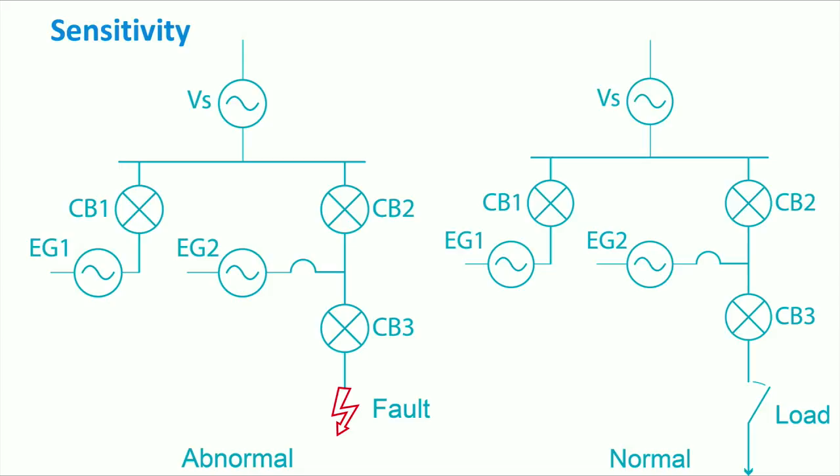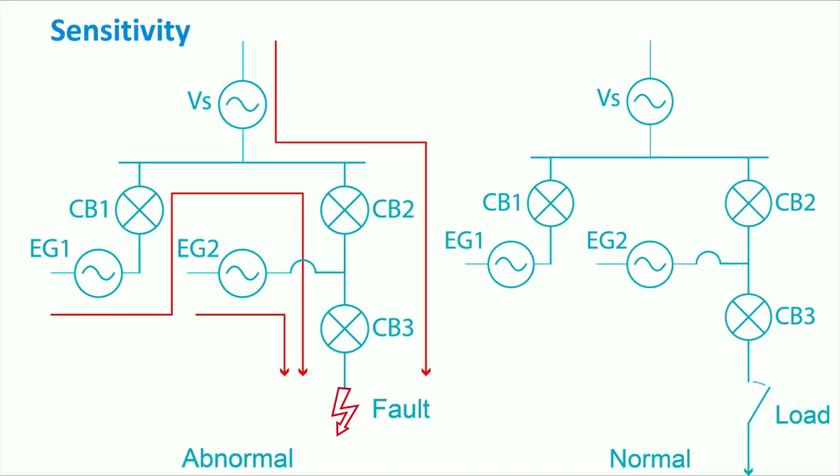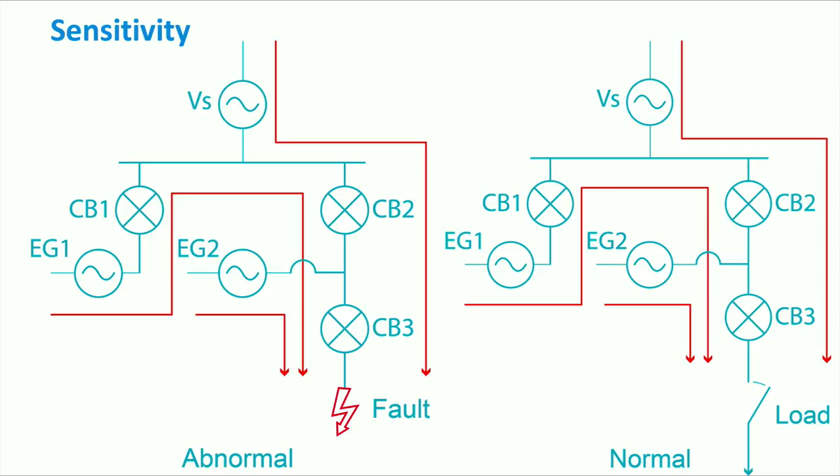When a fault occurs, on the figure on the left, the generators labeled EG in the drawing will start injecting more current in order to clear the fault. Note that also in case of load connection, the level of current increases in all distribution lines. So the protection scheme shall be fine-tuned in such a way that the overcurrent relays only operate during the fault conditions.